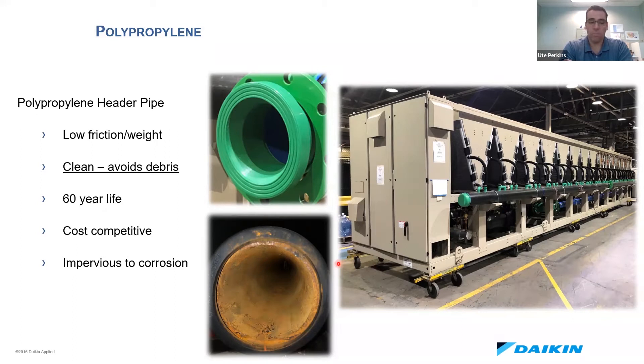I want to talk about two key points: it's impervious to corrosion and it's cost competitive. Some folks said it's more expensive — maybe per linear foot it might be a little more expensive — but when we looked at manufacturability it was a significant savings. Two people could lift that pipe into place, whereas you'd need a crane for steel piping. The other aspect that saved us tremendous time was cleaning: when we got steel pipe from the vendor, it required many hours of cleaning to reach the cleanliness we desired.